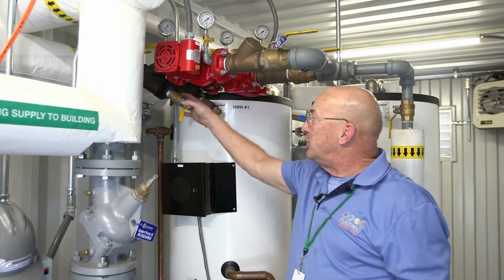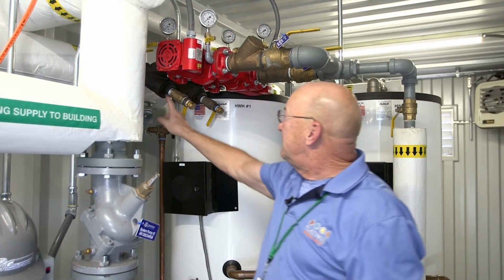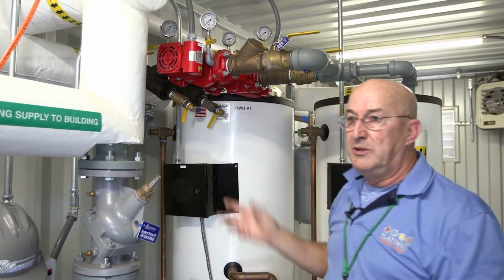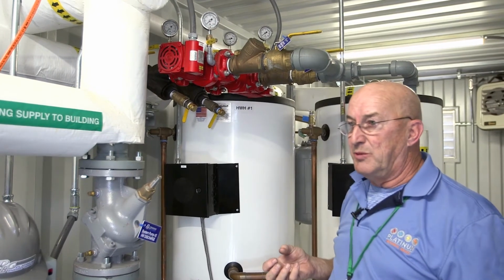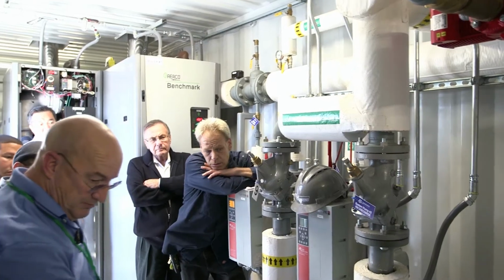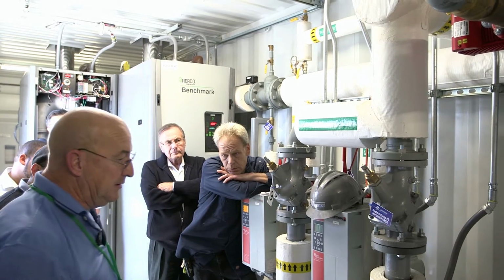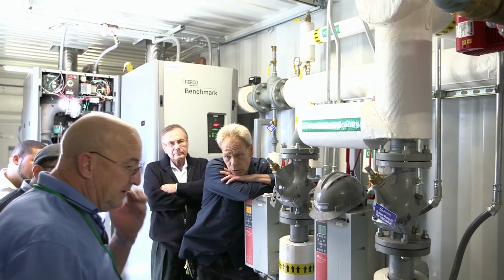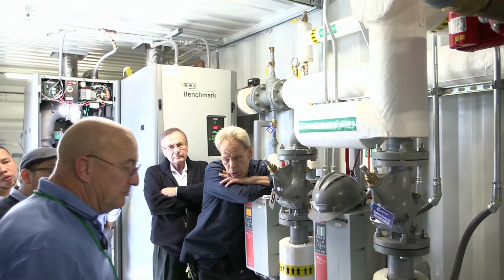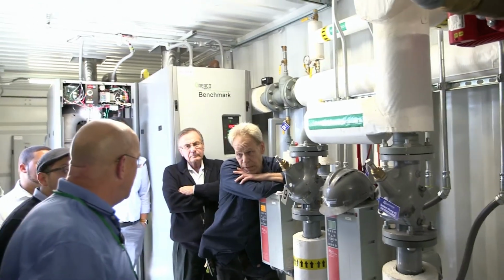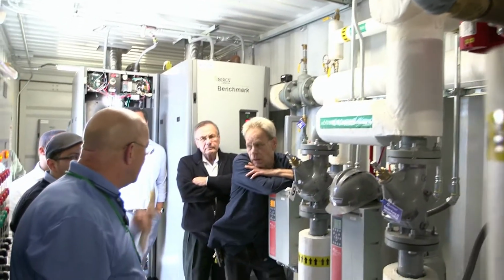Worst comes to worst, if you don't get any water out of it, you can shut the valves. Take a wrench here, unscrew it, pull the strainer out and clean the strainer by hand. There is a drain on both tanks. The amount of hot water you're going to go through here, I would say once a month you flush it down and clear off the bottom of the tank.